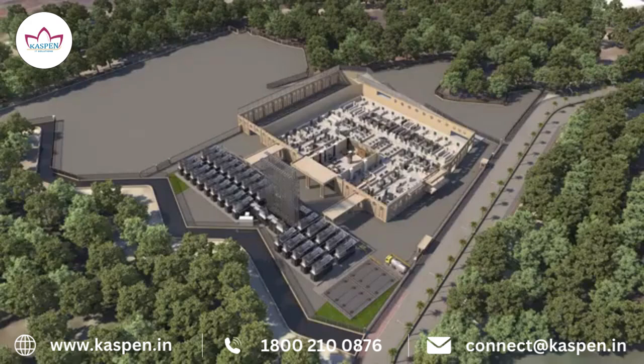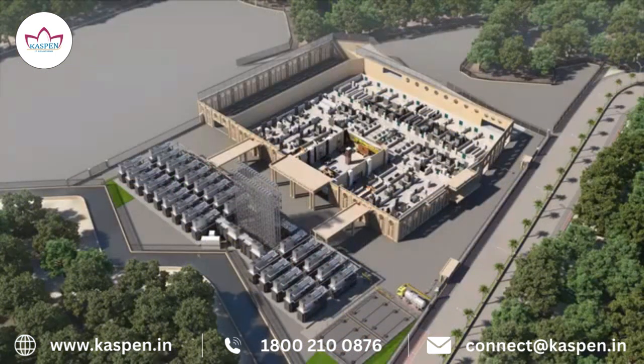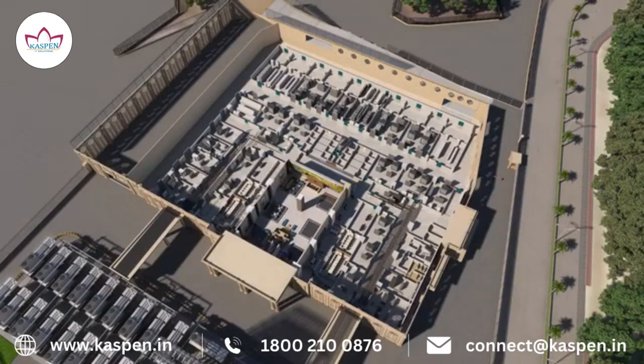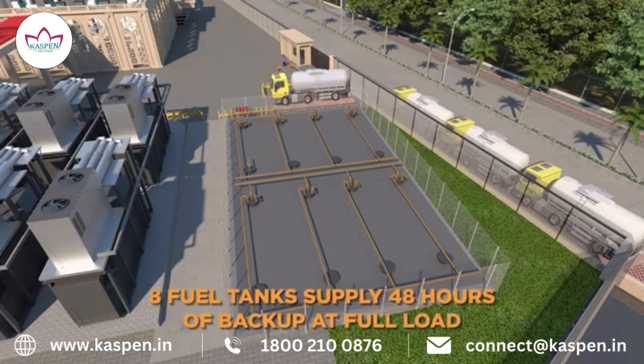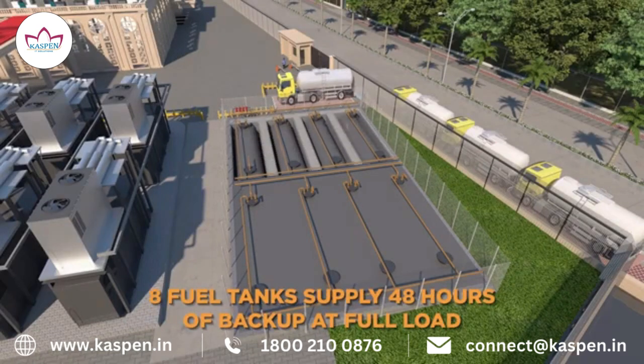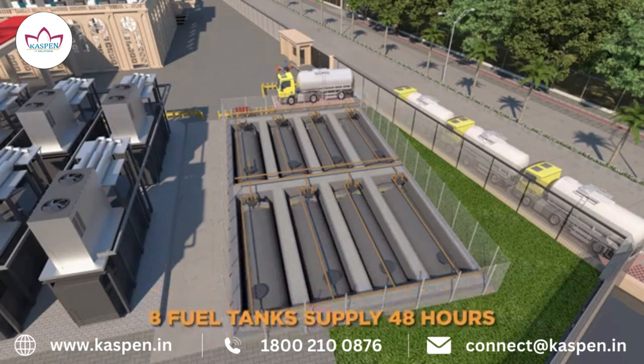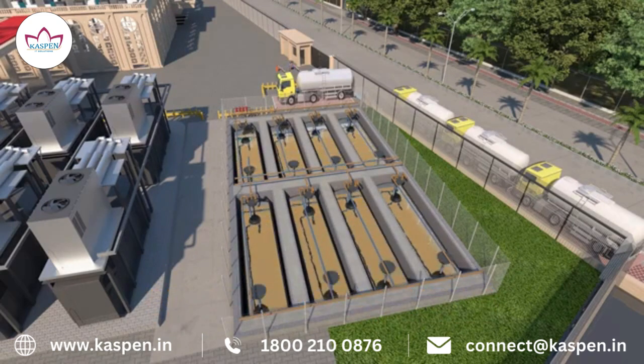racks. The utility feeder is backed up by an array of 32 diesel generator sets, each of 2.25 megawatt in N+2 configuration that supplies continuous backup power to the data center through an array of specially designed fire and water-resistant bus ducts. The diesel generator sets are backed by 600,000 liters of diesel fuel stored in underground tanks, ensuring 48 hours of uninterrupted operations at full load.